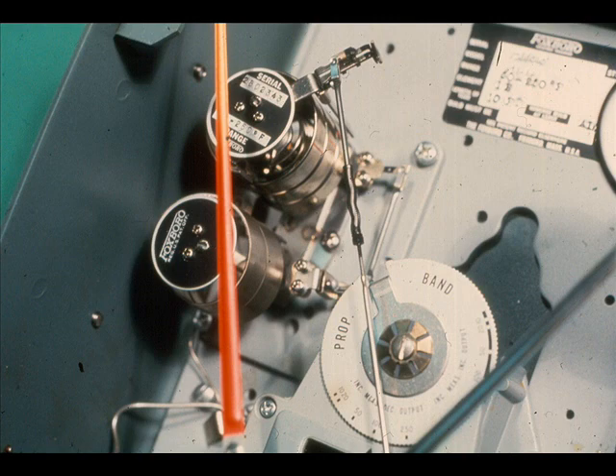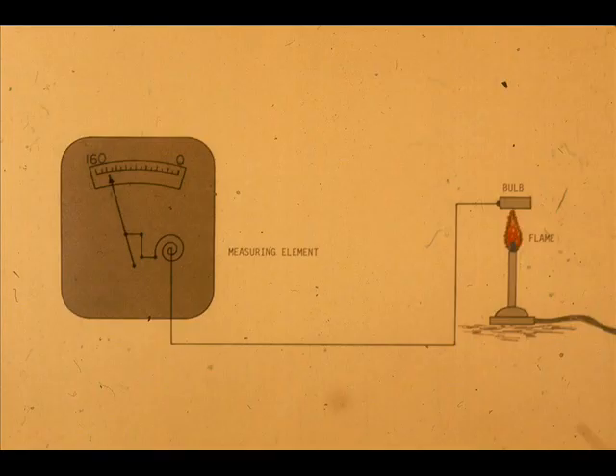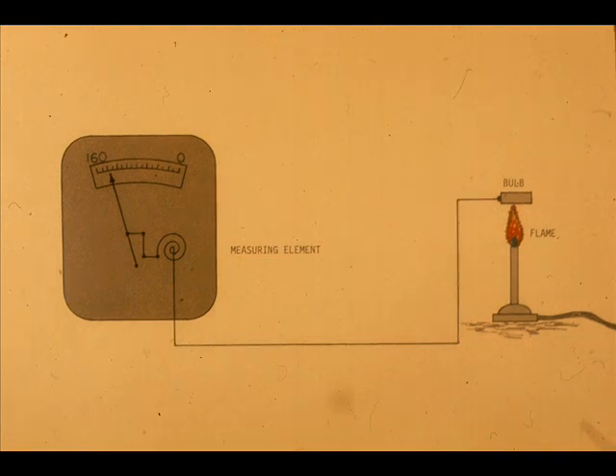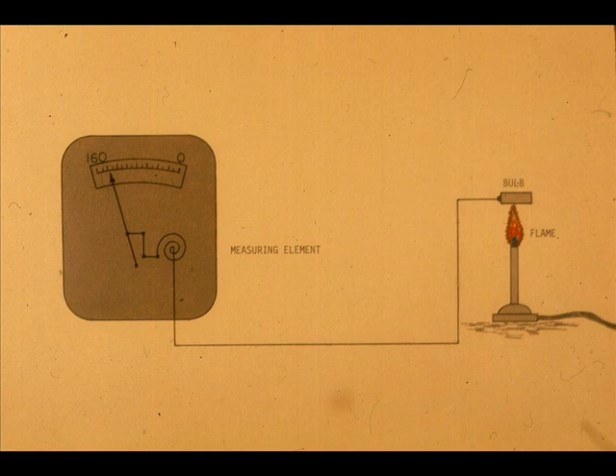Because the system is completely filled with liquid, any expansion must take place in the measuring element, since this is the only part of the system with spring characteristics. Force is transmitted equally throughout the liquid. Therefore, a slight change in volume at the bulb is sensed almost instantly at the measuring element. The response is almost instantaneous, but it is necessary for the entire mass of the liquid in the bulb to change to the new temperature before the final reading is correct.